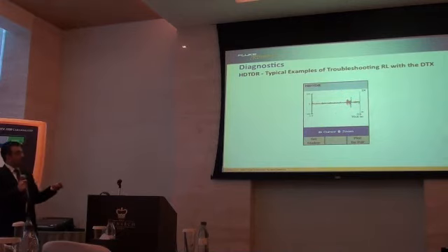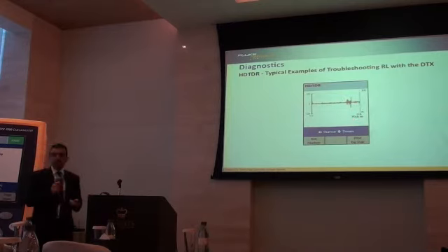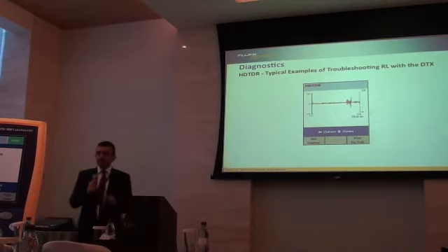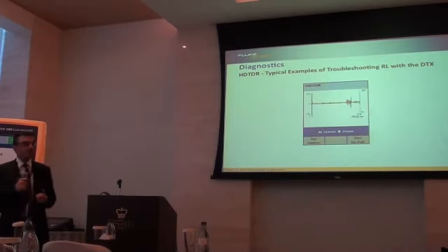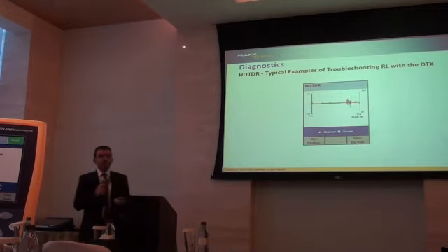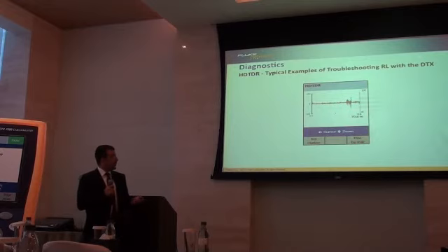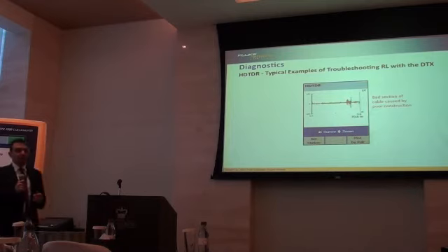So, if we look at a return loss, we see that at 70 meters here, I have a bad result. With experience, with more training, with what we teach in the CCTT training, you will come to know that if this happens in the cable when using the return loss tests, that means there is a bad section on the cable, that this particular point of the cable is bad.